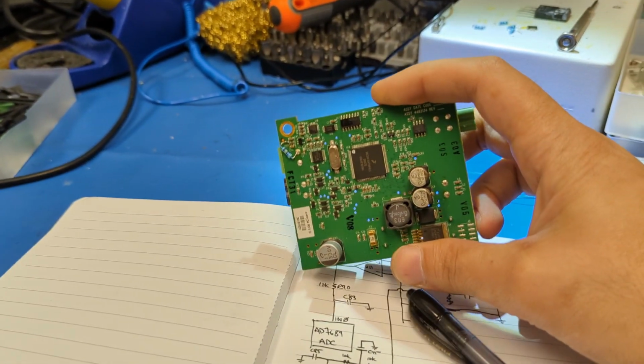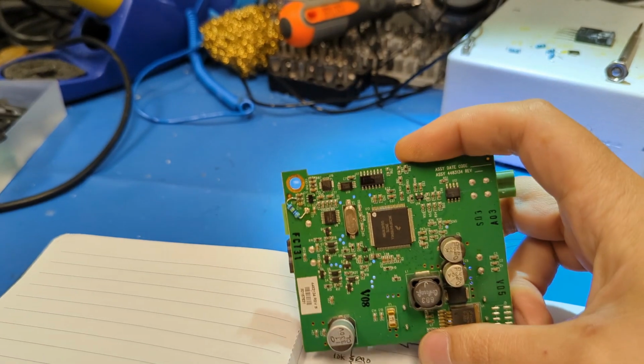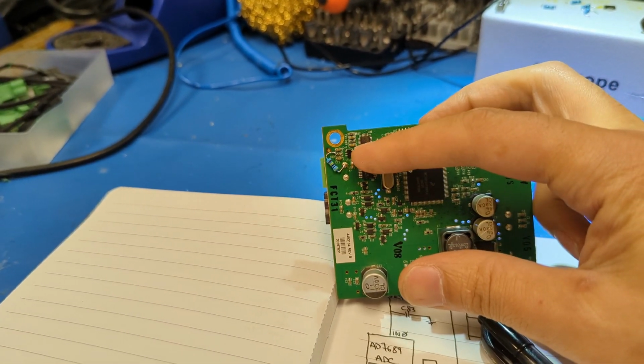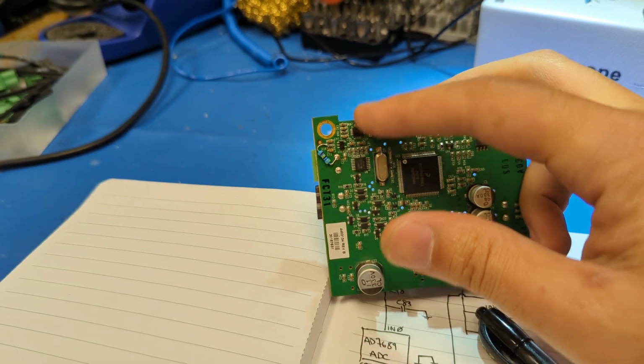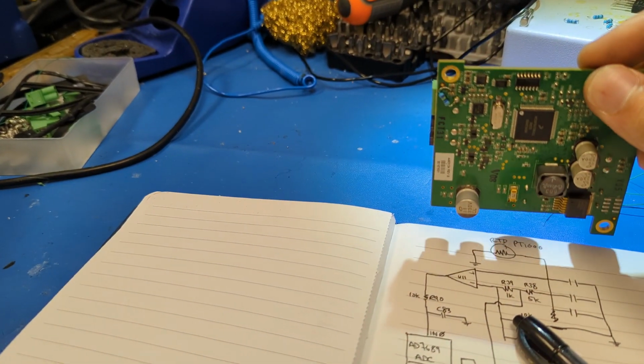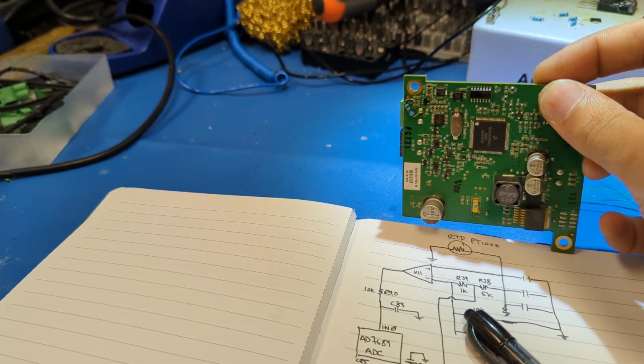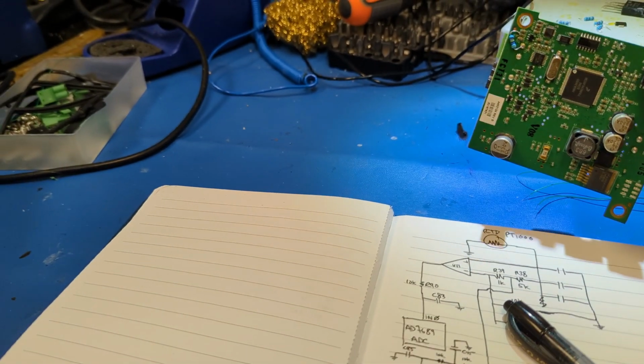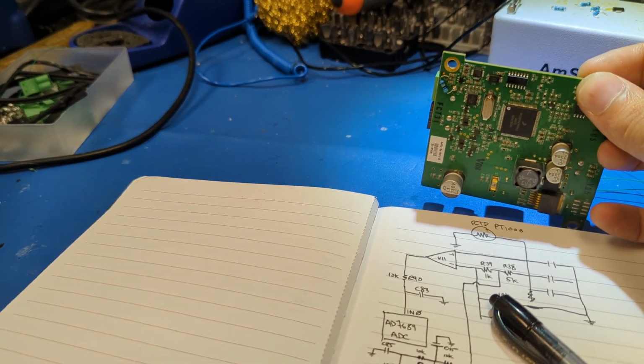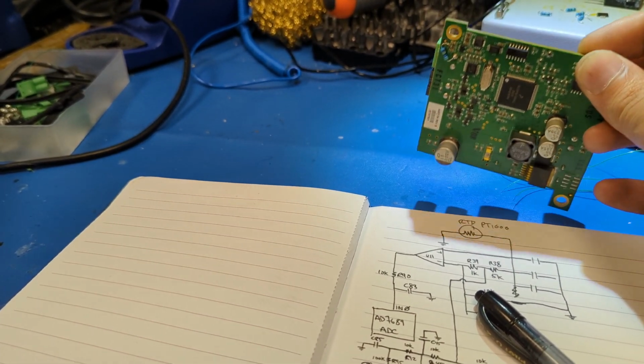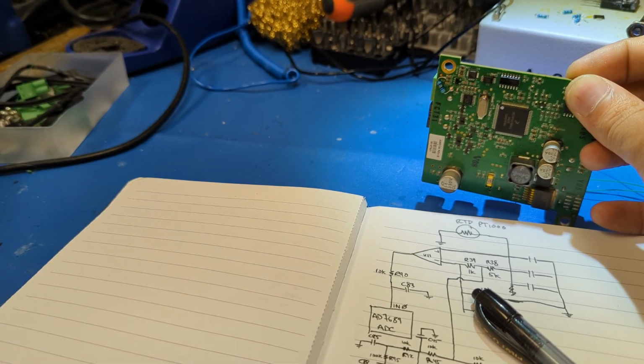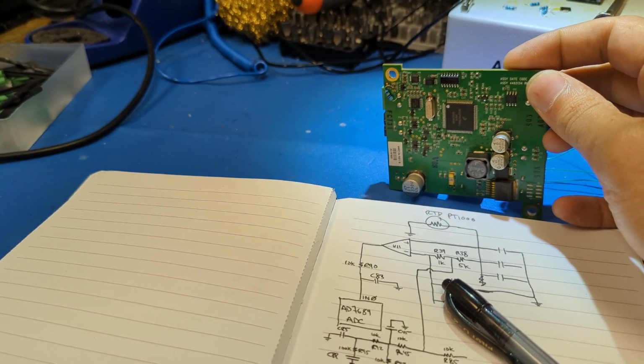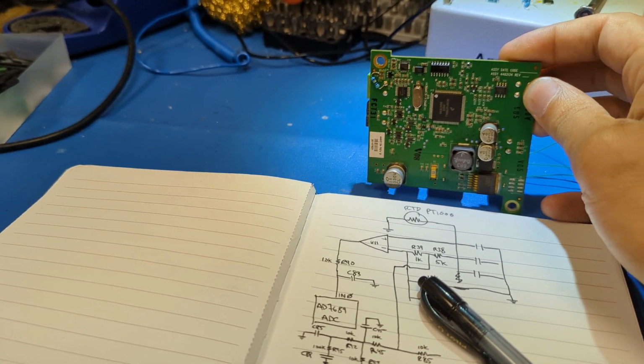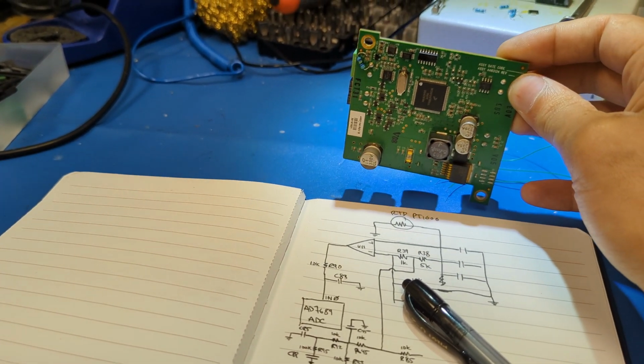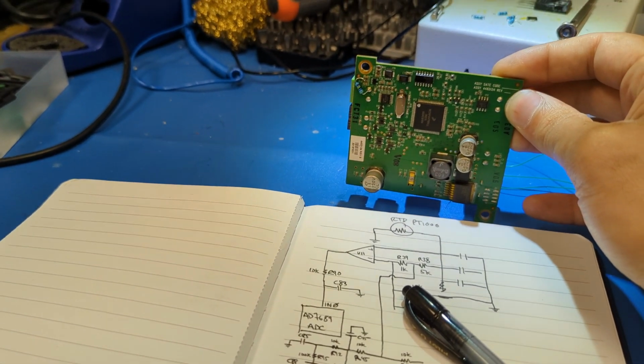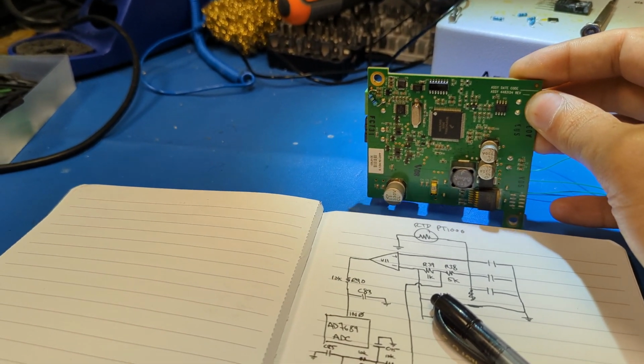Now, the problem with this mod is it could definitely be optimized, that's for sure. One of the problems is, if doing this exact mod, putting a resistor in parallel with R38, that's only going to allow you to get decreases in temperature. So, if your case is the temperature is too low, which I have never seen before in these instruments, I've only seen it get too high, unless there's something really wrong, and that's an entirely different situation. But in most cases, the temperature is too high, and this will work just fine for this type of modification.